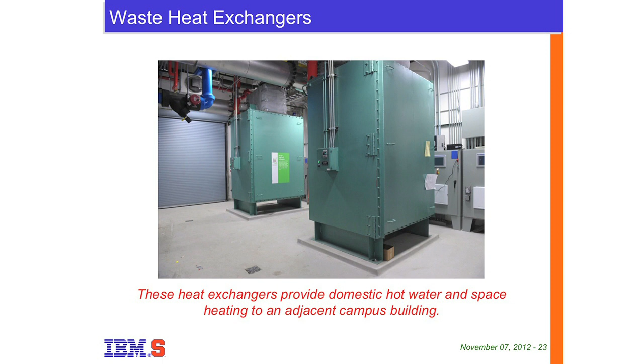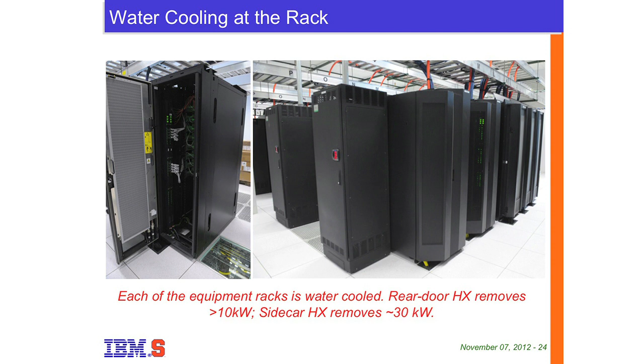These are the heat exchangers. You can see one of these heat exchangers here, the rear door heat exchanger. In essence, in the back of the rack, you put a heat exchanger that looks like a car radiator. It does not have a fan. It relies on the fans in the servers to move the air through it. The pressure drop through it is very small. And that one can remove in excess of 10 kilowatts of heat from a rack. Most racks are about that. It can actually do more than this.